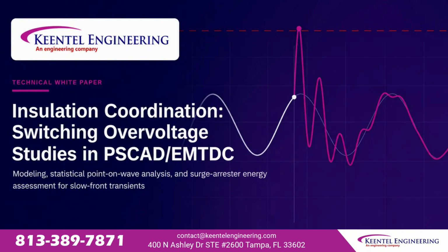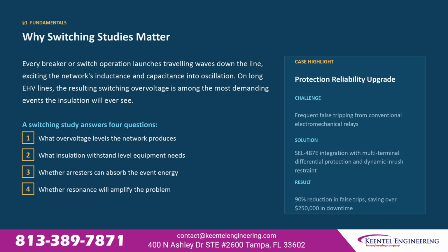In this video, we break down how switching overvoltage studies are built and run in PSCAD/EMTDC, covering network modeling depth, transmission line model selection, surge arrestor assessment, statistical point-on-wave methodology, and how to read results against equipment withstand levels. 3 case studies show what these numbers look like in practice, followed by 10 frequently asked questions. A switching overvoltage study answers 4 questions.